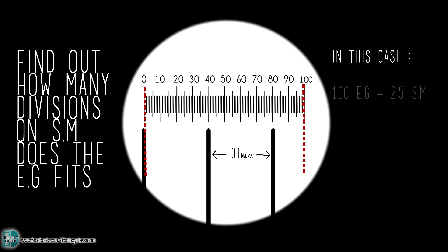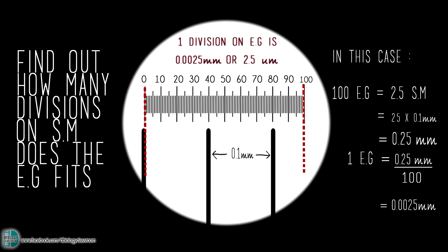In my example, the total length of the eyepiece graticule fits into 2.5 divisions on the stage micrometer. Since each division on the stage micrometer is 0.1mm, 100 divisions on the eyepiece graticule is equal to 0.25mm. Divide this value by 100, you will find out that each division on the eyepiece graticule is equal to 0.0025mm or 2.5 micrometers.